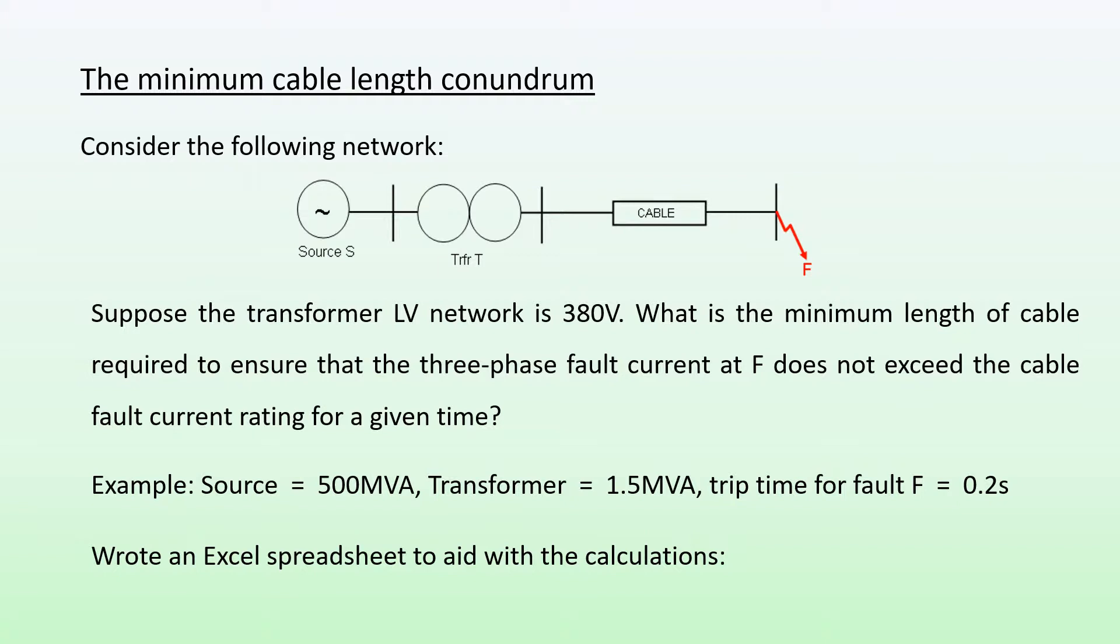For an example, I have a source which is 500 MVA, transformer is 1.5 MVA, and my trip time for the fault F is 0.2 seconds. Notice my cable has a fault at its end, which means it's a through-fault with regards to my cable. I wrote an Excel spreadsheet to aid with the calculations.